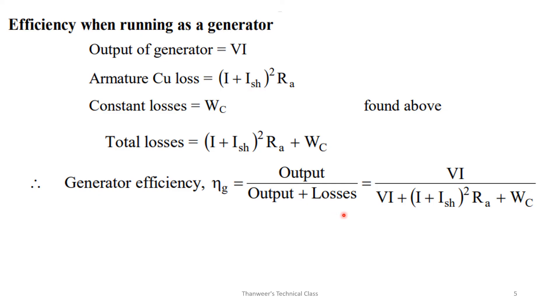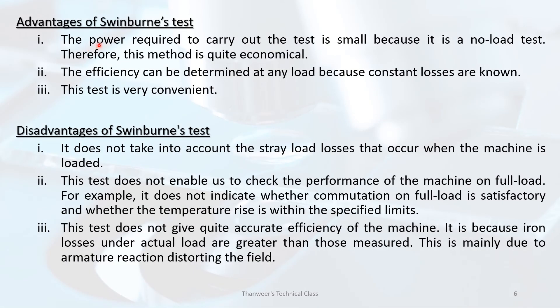Now, the advantages of Swinburne's method: the power required to carry out the test is small because it is a no-load test, therefore this method is quite economical. Since constant losses are known, the efficiency can be determined at any load.